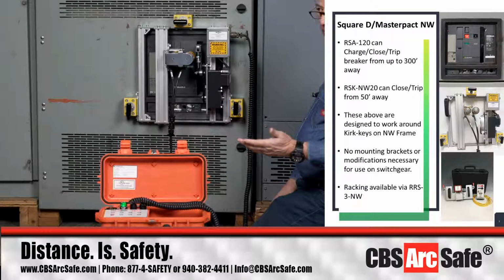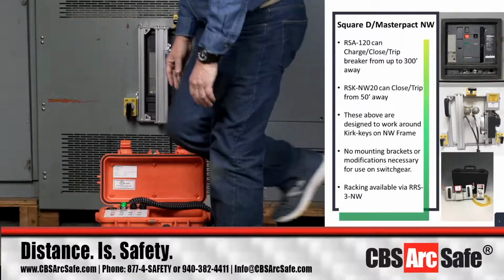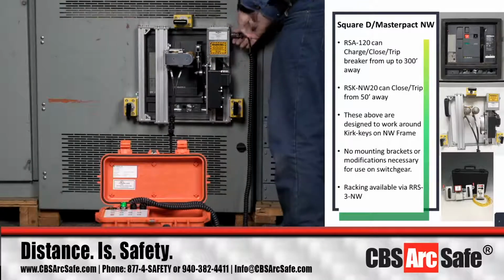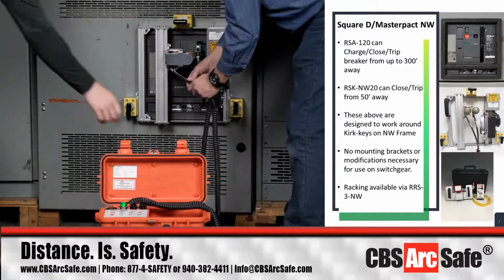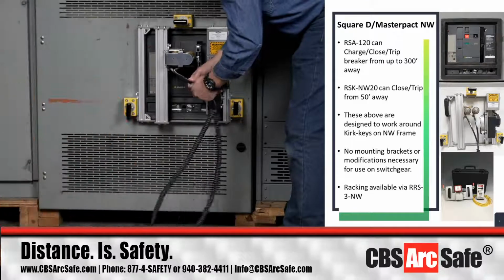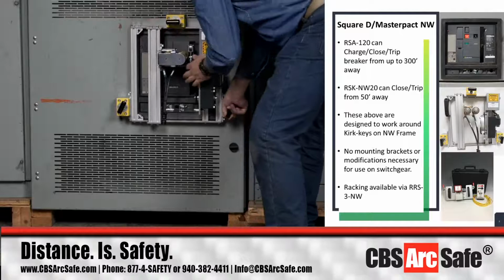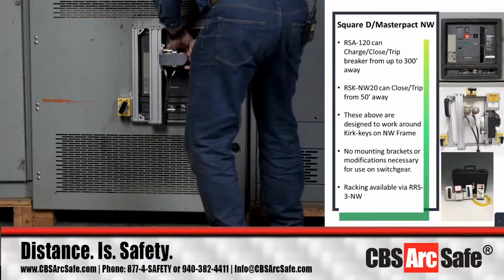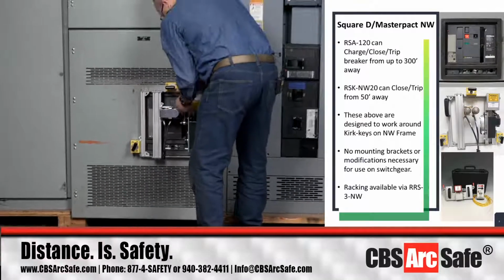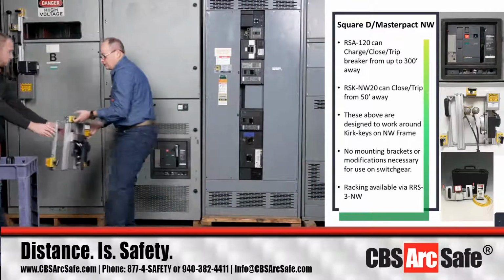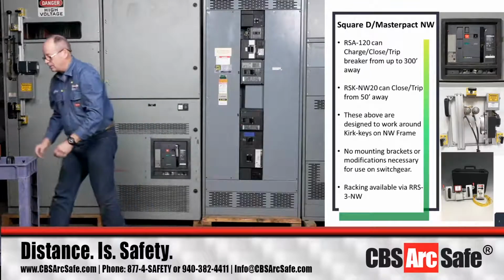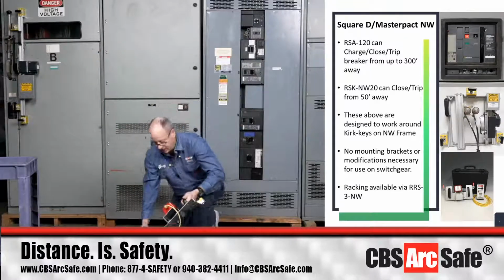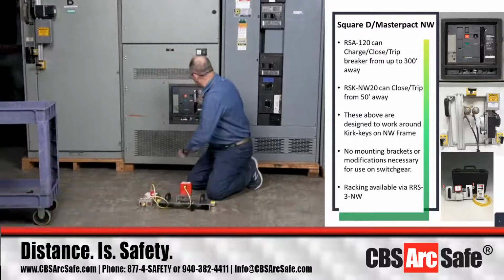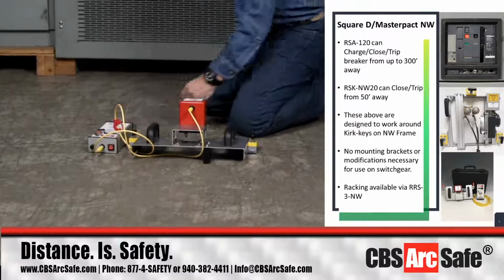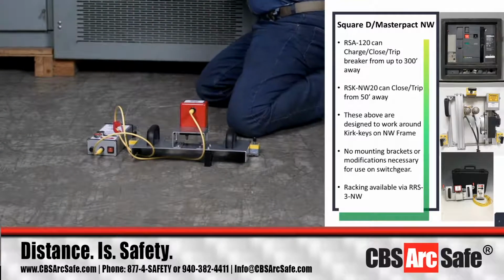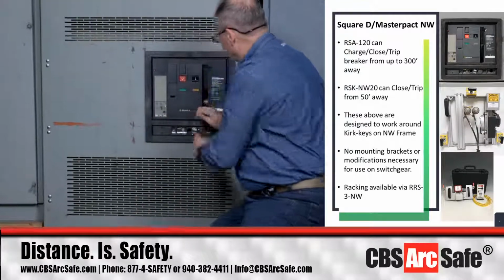Besides the RSA 120, we also have the NW20, the RSK NW20. And that's from our Martech lineup, and is for simply closing and tripping the circuit breaker. So if all you need to do is close and trip the circuit breaker, and you're going to manually operate the charging arm yourself, this is an ideal setup for that. It locates very easily onto the circuit breaker, so I'm going to finish taking the RSA 120 handle off. I've got to manually charge it though first. 1, 2, 3, 4, 5, 6, 7. So now we've got the breaker charged.